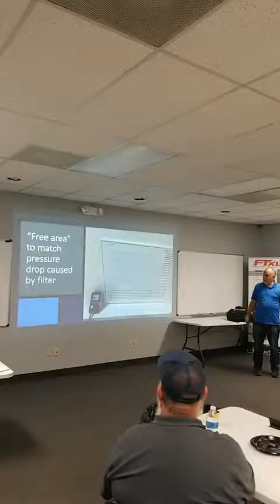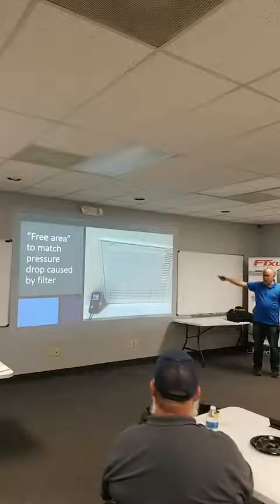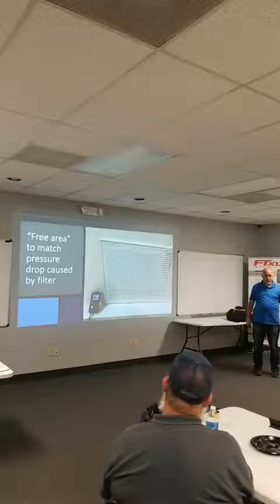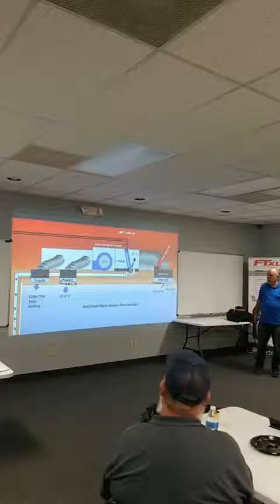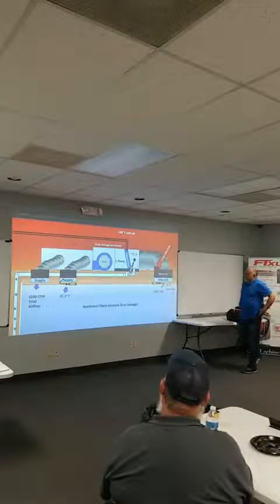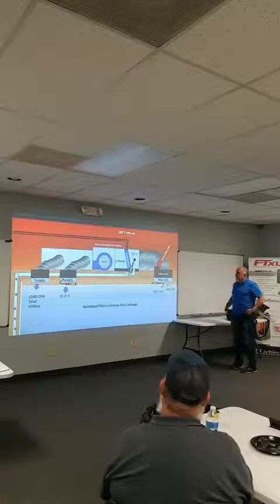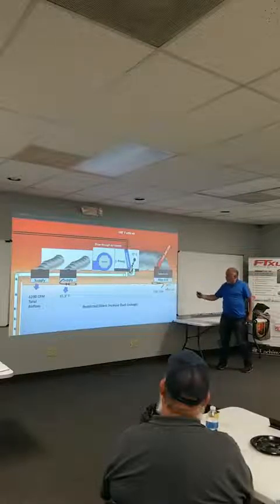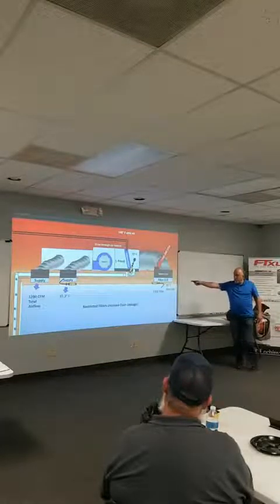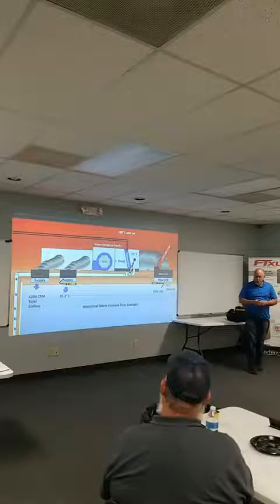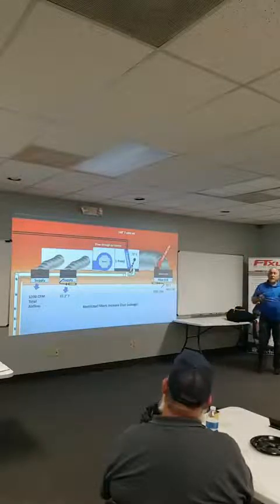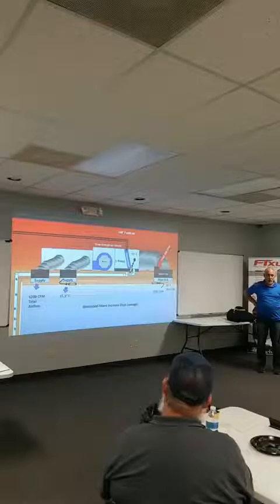Took the filter out and blocked it with paper, right? So no air is getting through the paper. So that's my effective grill area right there with that filter in, because the pressure drop is so high. Right? Now, when you're using Measurequick, we test from inlet to outlet. So when you're looking at this here, we always want to put the probe on a filter grill and on the closest supply. I know that's not possible in every situation, like some rooftop systems we can't get the stuff up top where it needs to go, but this is the way the software is designed.